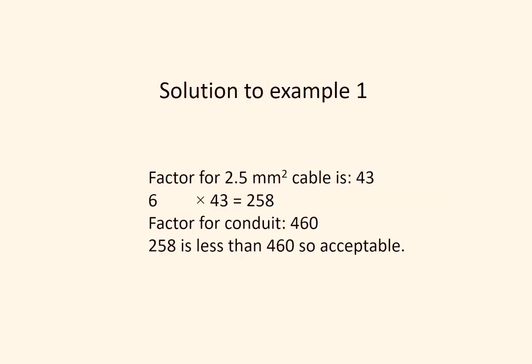And so the solution is, the factor for 2.5mm cable was 43. I had 6 of them, so it's 258. The factor for the 20mm conduit was 460. So that is acceptable. That's quite easily going to fit inside that conduit.